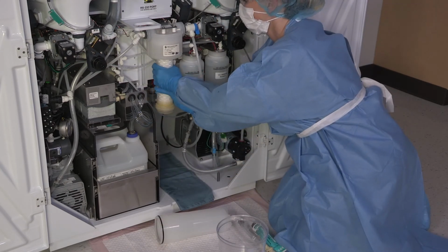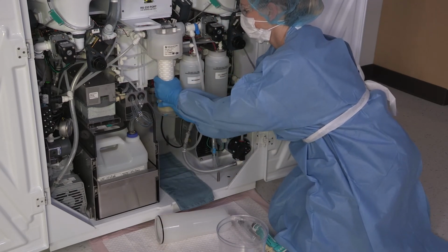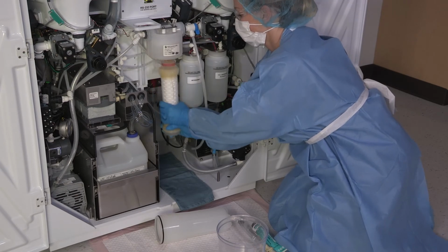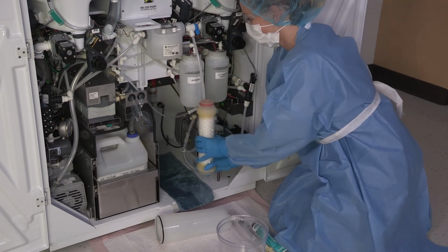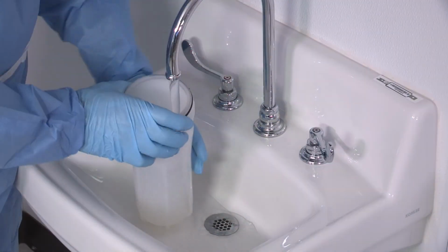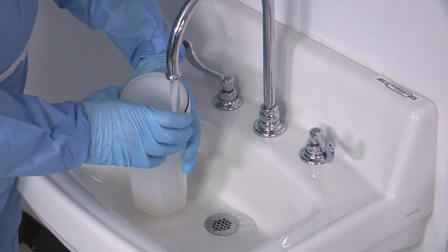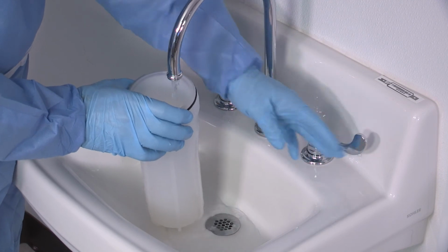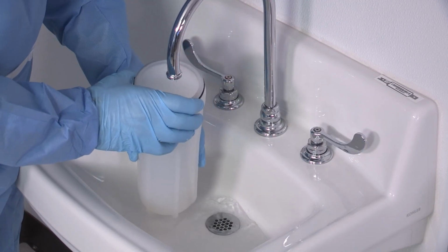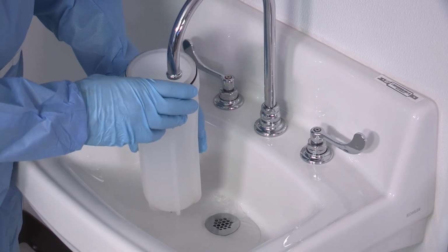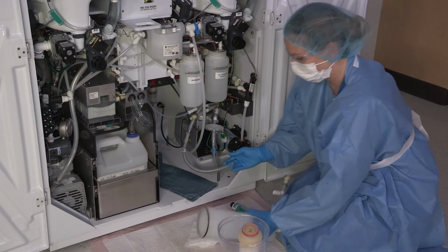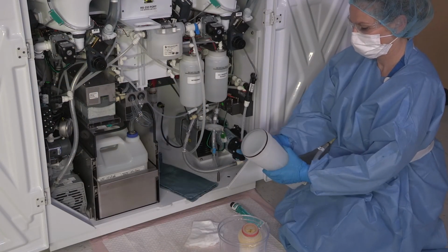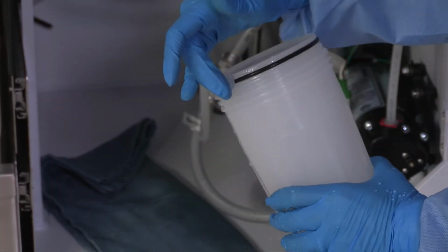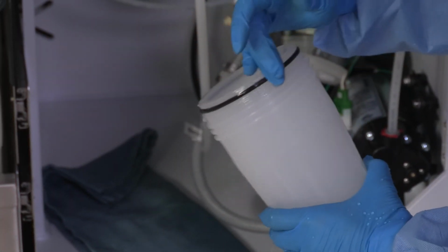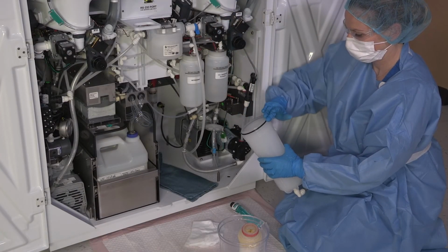To remove the filter, rotate the filter 1/2 inch towards the left to unlock the filter. Pull the filter downward to remove and discard. The filter housing can be cleaned by washing with neutral pH, low-foaming, medical-grade detergent, such as Intercept detergent, then rinsing thoroughly. Inspect the O-ring for twists, wear, or damage. Replace if needed. Apply high-vacuum grease to the housing's O-ring and threads if needed to aid in installation and sealing.